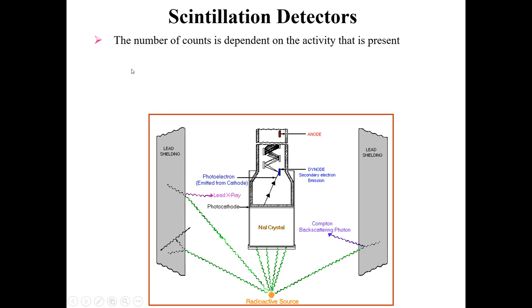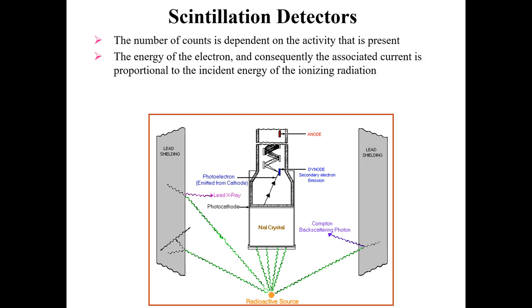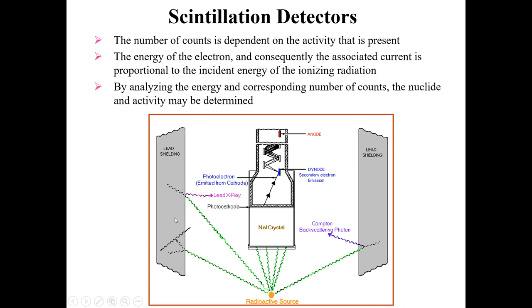The number of counts produced is dependent on the activity present. The energy of the electrons produced, and consequently the associated current, is proportional to the incident energy of the ionizing radiations. That is, the current produced is proportional to the energy carried by the incoming radiation — in this case falling on the sodium iodide crystal.